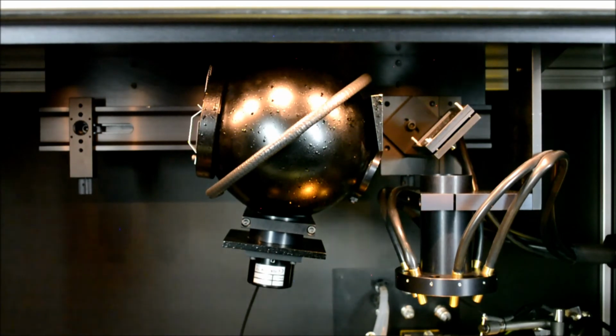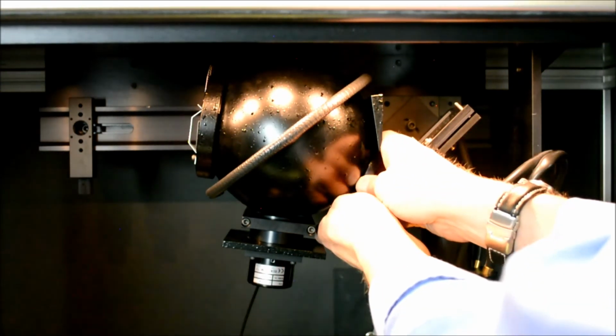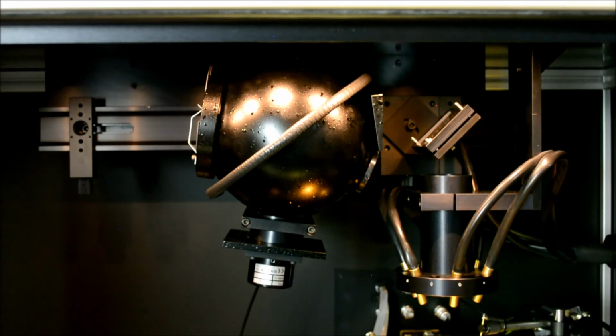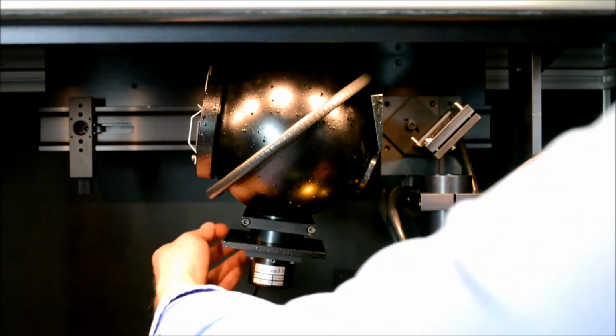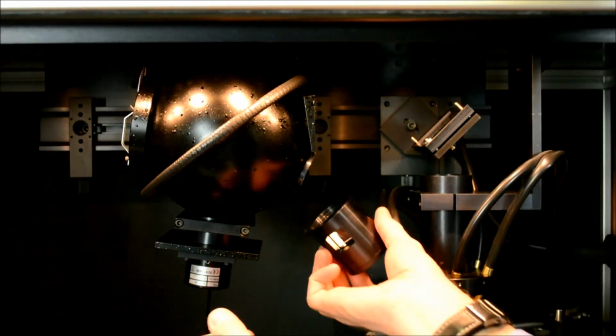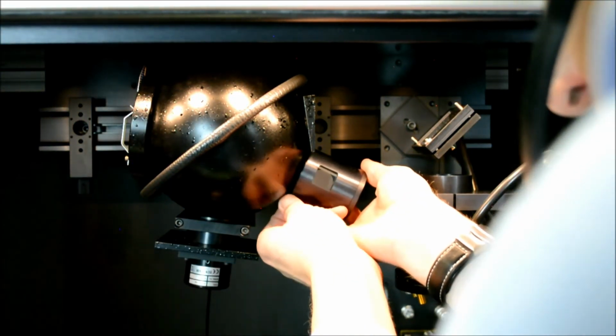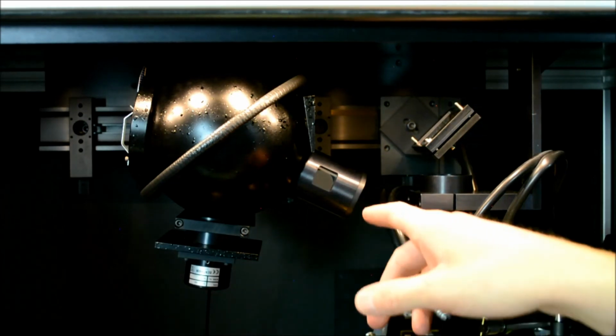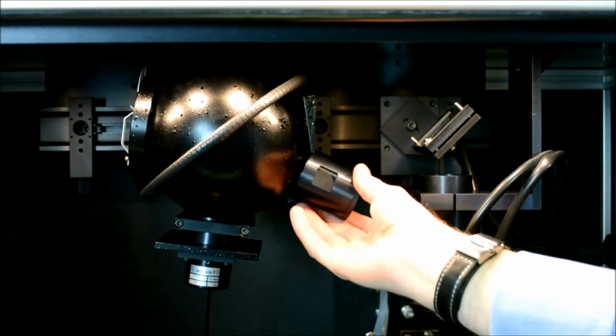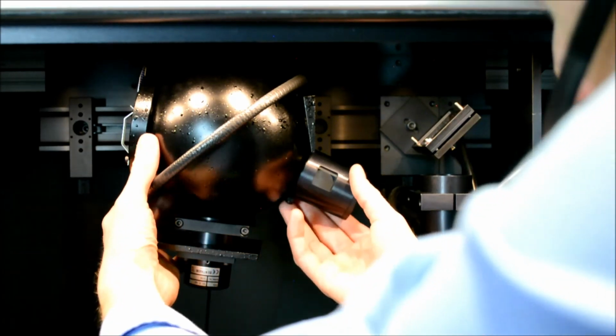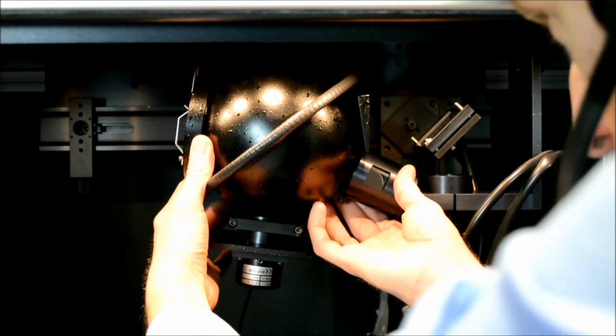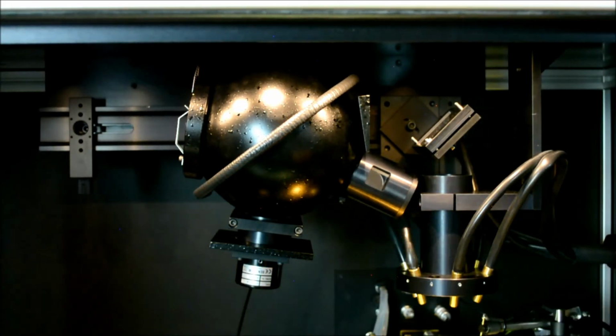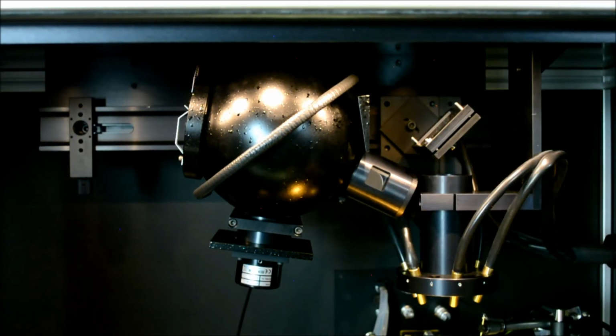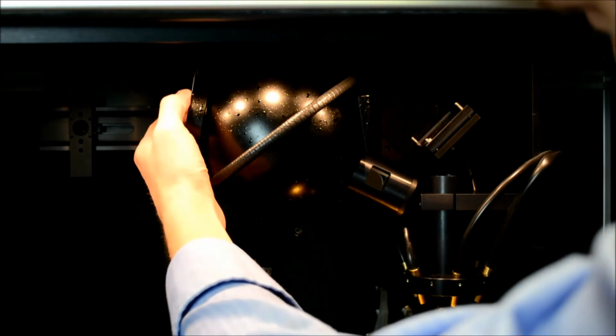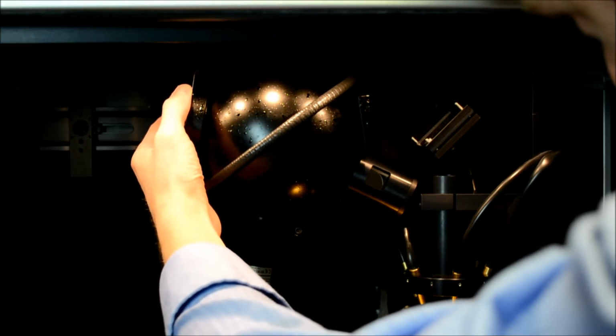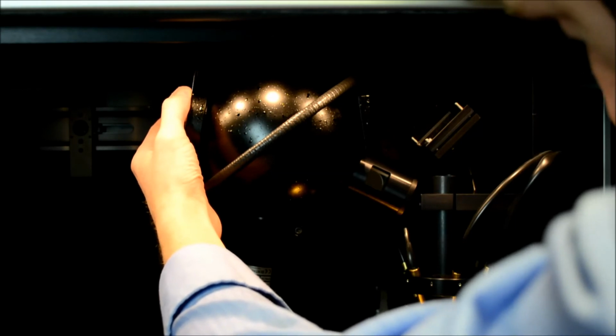To fit the port viewer, we need to remove the specular reflectance cover, translate the sphere somewhat to fit the viewer in place, rotating the position so that one can see the plane of the sample, and push this back towards the right hand stop. By viewing what one sees in the viewer, one can adjust the position of the sample to ensure that the beam falls between the electrodes.